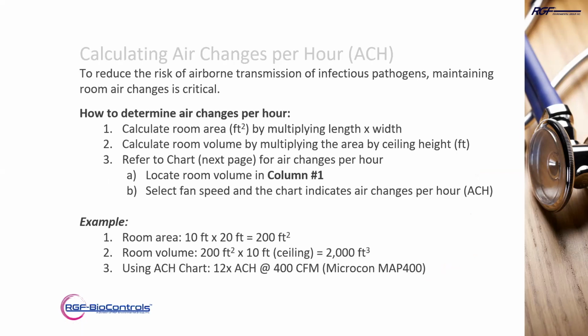So how do we calculate air changes per hour? We get the area, then the volume - pretty basic math, you can see the example. 10 feet by 20 feet gives us 200 square feet. For volume, 200 feet by 10 foot ceiling height gives us 2,000 cubic feet, which we plug into the chart on the next slide.